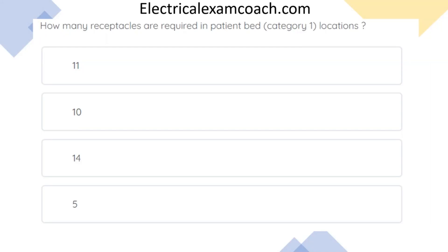How many receptacles are required in a patient bed category 1 location? The correct answer is 14. Believe it or not, there are 14 required receptacles in this category 1 location.